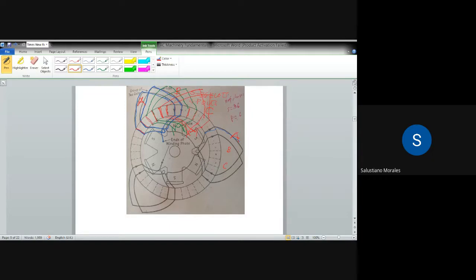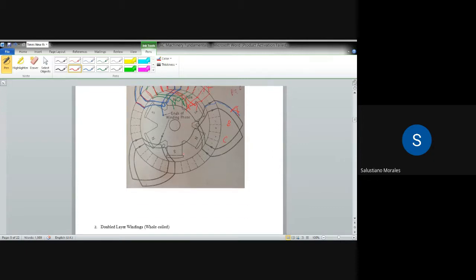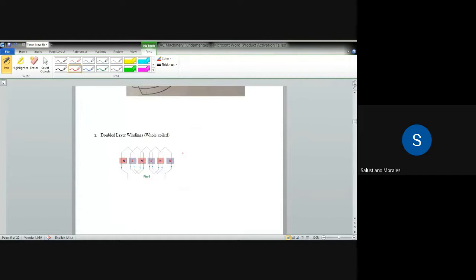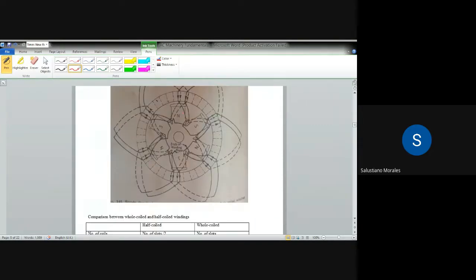The arrangement for the armature of an AC generator is usually similar to lap winding, but the only difference is that the coil ends are not connected to a commutator. Instead, the coil ends are connected in series to produce a certain direction of current. After connecting phase A, B, and C together, you can connect the winding as Y or delta.